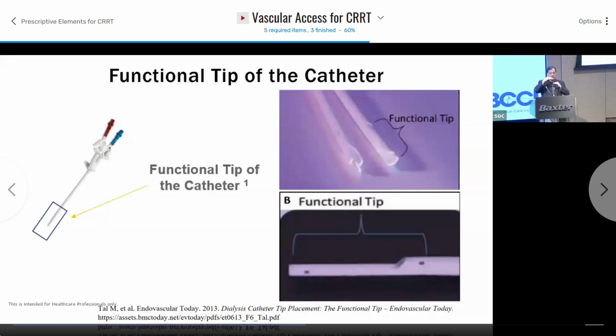The top end of the catheter, 2 to 3 centimeters above the tip, is where the suction of the blood is occurring, and that has to be away from the walls. That's why you need it down. If you're closer up, veins are coming in and out, and your flow changes very quickly along the SVC. That's why you need it down, to make sure that your functional tip is in that high flow region, not just the tip.